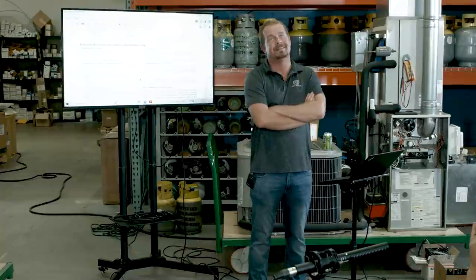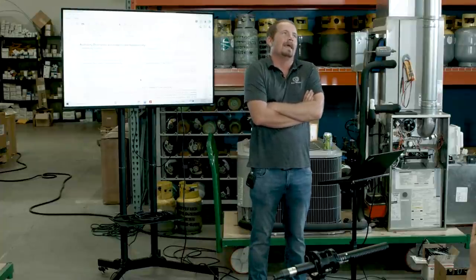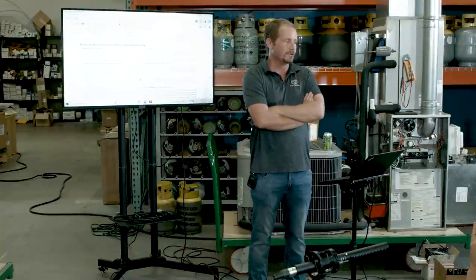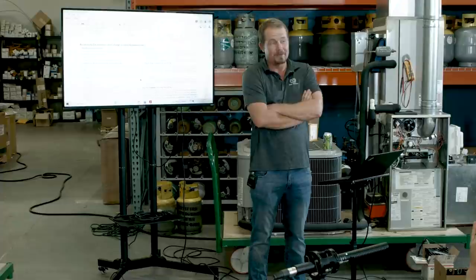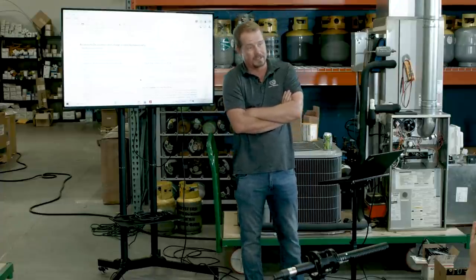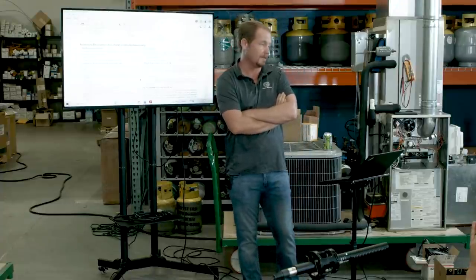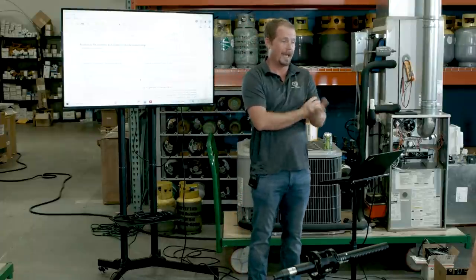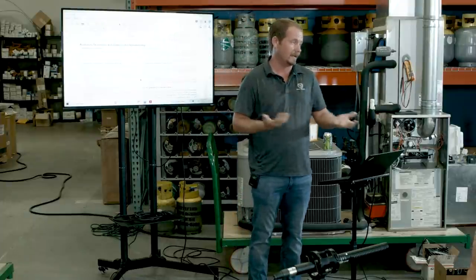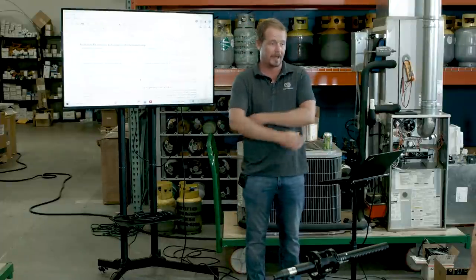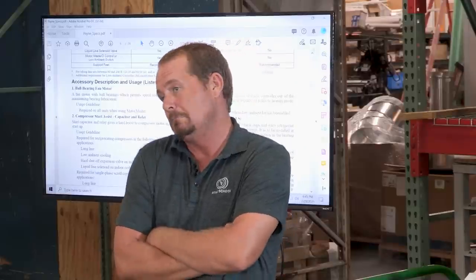Now, am I being pedantic to say that we should do this every time in long line applications? Maybe, but I'm telling you what the manufacturer says for this particular piece of equipment. That's not going to be the same for everyone. Some pieces of equipment have hard shutoffs inside, outside on a heat pump system, and even Carrier is going to that on a lot of systems now. So it may not be something that happens for that long moving forward.